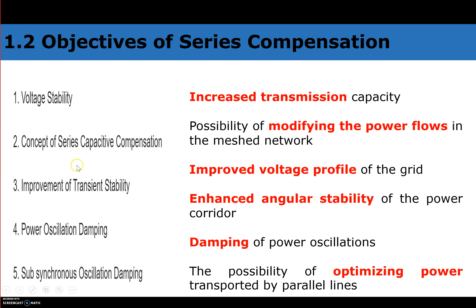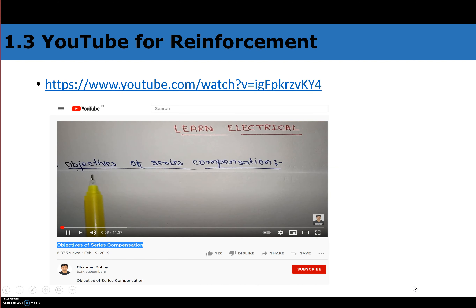The objectives of series compensation include: improving voltage stability and power transferring capability, improving transient stability, damping power oscillations, and damping sub-synchronous oscillations. It can increase transmission capacity, modify power flows in a mesh network (since changing reactance of one line changes power flow through all connected systems), improve voltage profile, enhance angular stability, and optimize power flow transmitted by parallel lines.